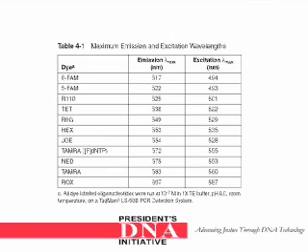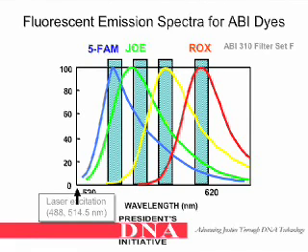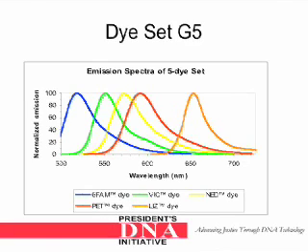This table shows the maximum emission and excitation wavelengths of some of the commonly used dyes in capillary electrophoresis. Here is a depiction of the fluorescent emission spectra for the ABI dyes, with laser excitation occurring between 488 to 514.5 nm. This is dye set G5: instead of four dyes, there are five dyes, used in the ABI Identifier kits.